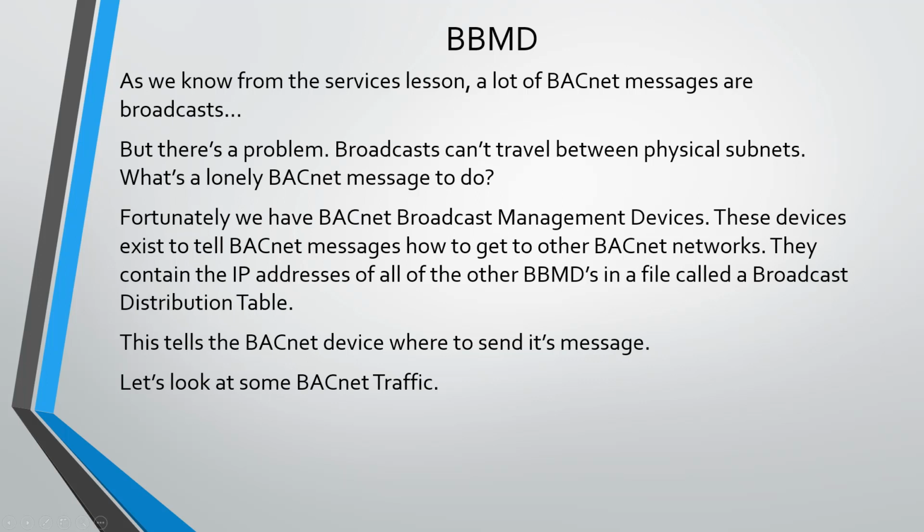Now, BBMDs are another topic that is very difficult for folks to understand, but it's because they just haven't been explained to them. I just went through how broadcasts can't travel between physical subnets. But with BBMDs, they can. We have these things called BDTs, which are broadcast distribution tables, and they store the BBMD addresses for the remote BACnet networks. This is how your BACnet traffic gets sent from one IP network to the next. So let's take a look at that. We've already taken a look at it a little bit, but let's take a look at it in greater detail.